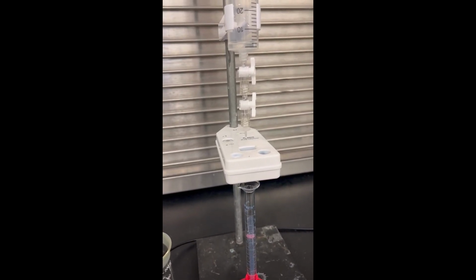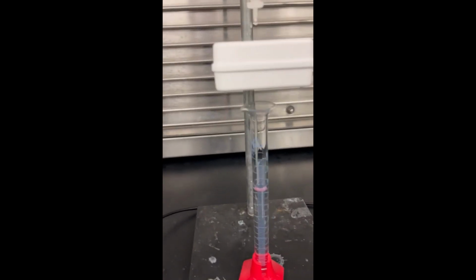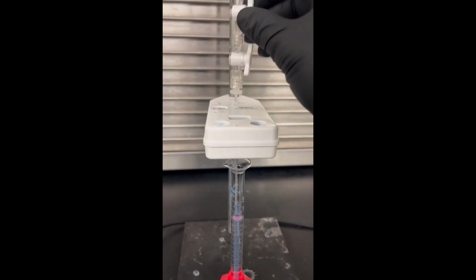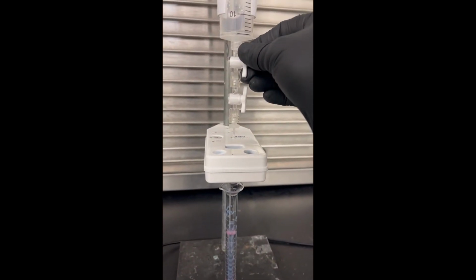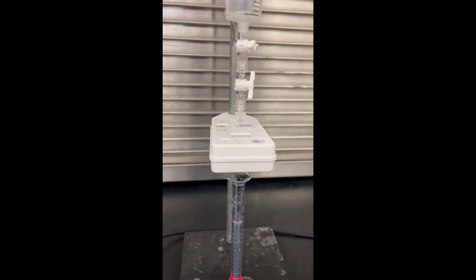Once you stop the flow, measure the amount that is now in the graduated cylinder and subtract 3 milliliters from it. This calculated value is what you put in the standard value field. If you want to check that you did it correctly, then divide the sensor value by your calculated value. You should get about 36 drops per milliliter. If you got below 35 or above 37, then you probably want to check with your TA or instructor before proceeding. Finally, you'll select Set Calibration and OK, and you can continue setting up your experiment.